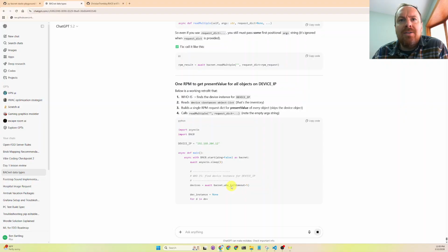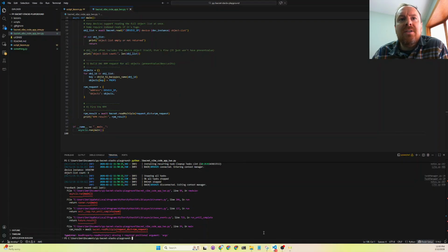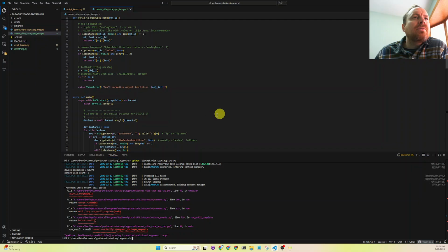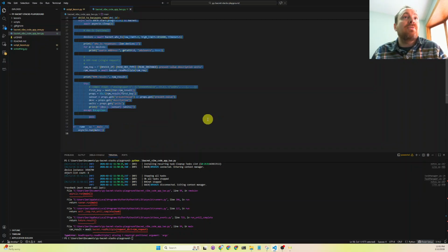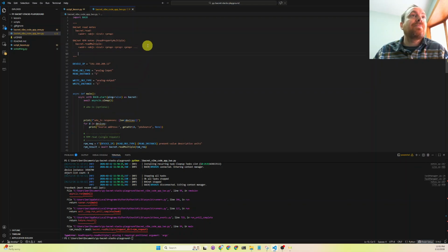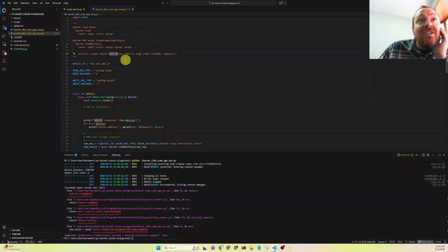I took away our whois range, which I don't like. Did that do that here? Yeah, did I here? So I'm gonna keep that as a note. I think this is super useful. Like what we were talking about before, don't do a whois on a live BACnet site. People only do that during the setup of a building automation or IT or IoT platform, because this is a global broadcast.